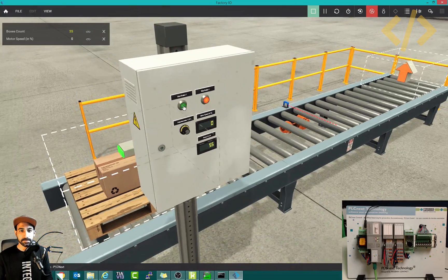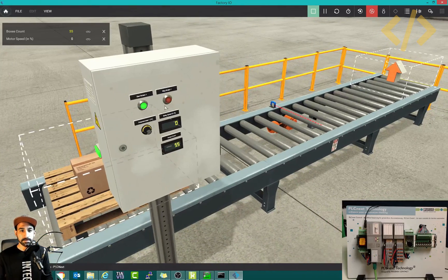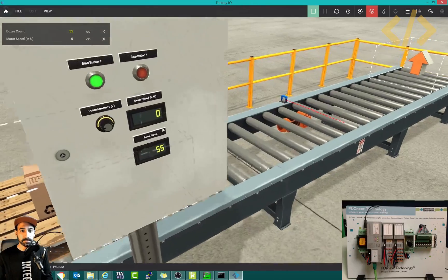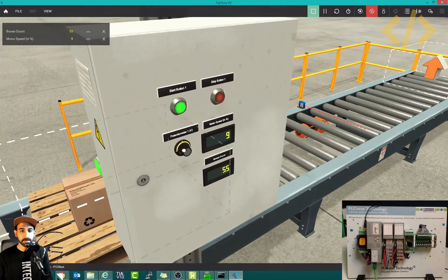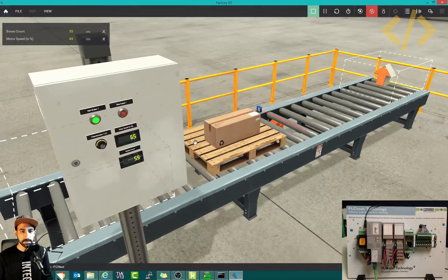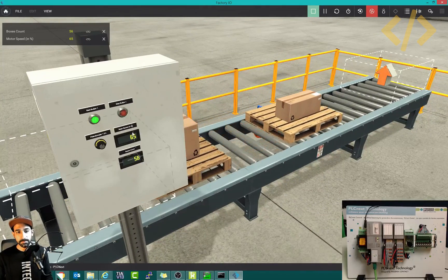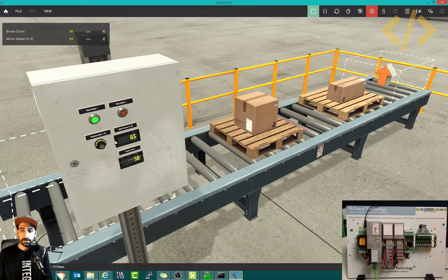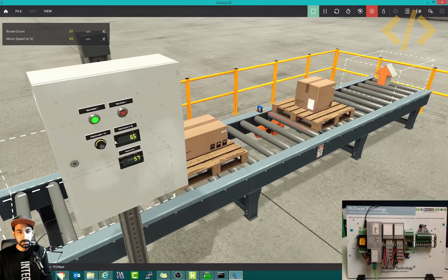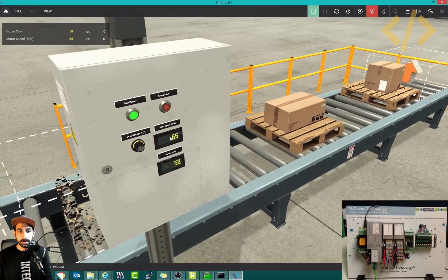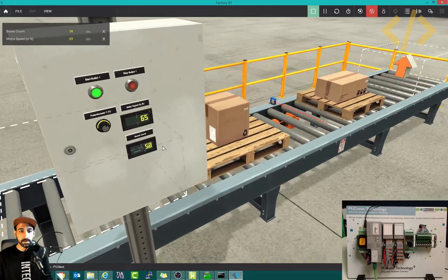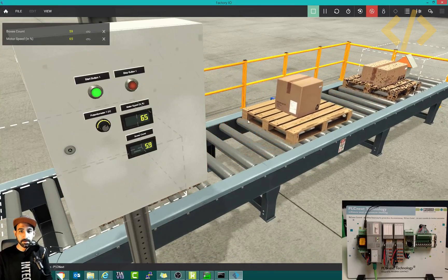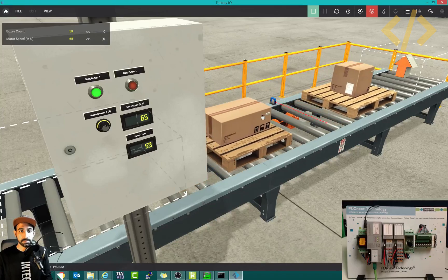If I click start, this command is going to the PLC. At the moment the speed is zero, so I will increase. This is 65 percent speed. The start command goes to PLC, the speed command goes to PLC, the logic is being solved which runs the motor at 65 percent speed, and you can see the boxes count coming here from this diffuse sensor.